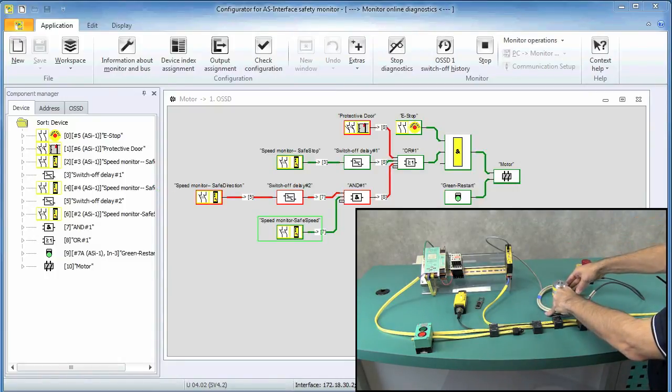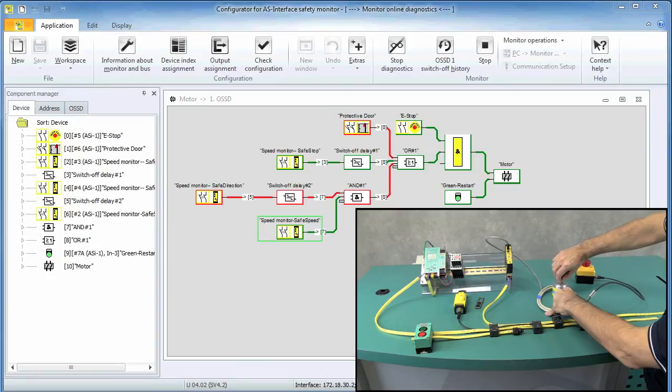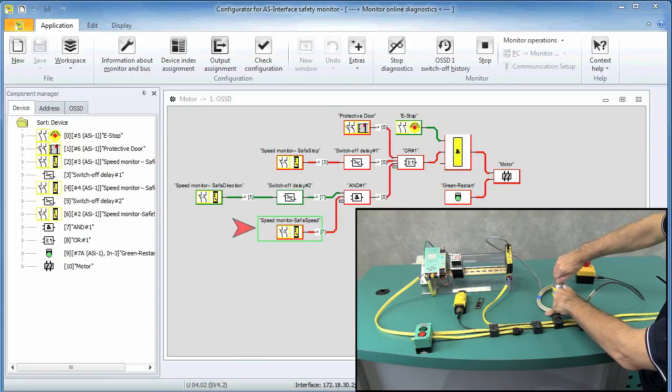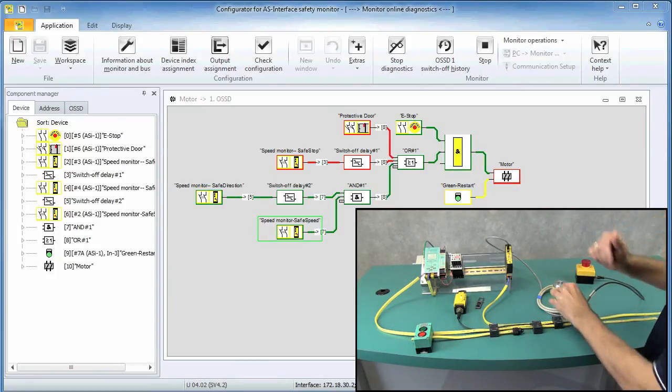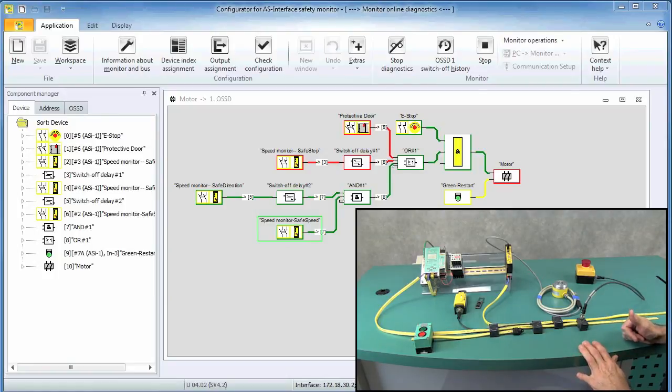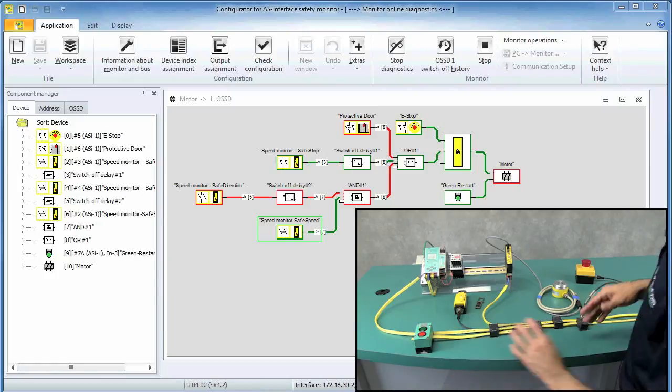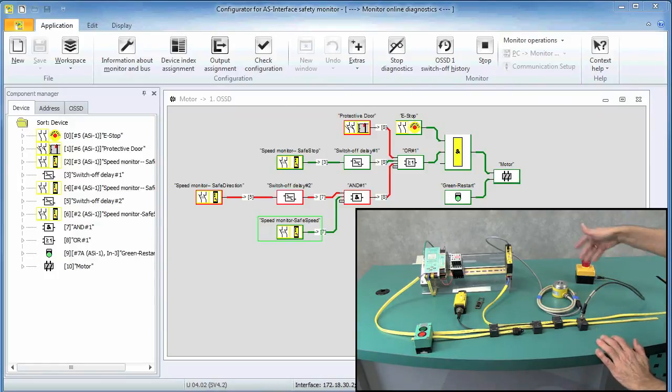Should due to a fault the motor ever spin at an excessive rate, we expect an immediate shutdown and the contactor drops out.